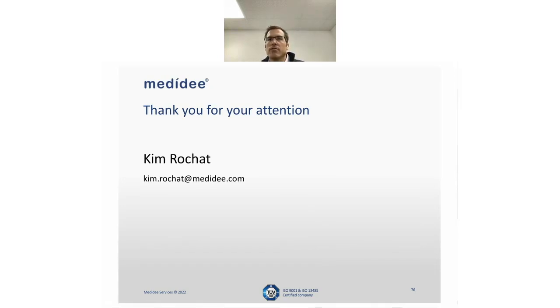I take the question of Stephanie. What is the situation if you add a medical software to an existing medical or combination product? If the intended use stays the same, but the device can now track through the added new software, is the regulatory path the same, including the clinical evaluation? Yes. So if this new software that you will add to the existing software, you need to define its regulatory status. So maybe it's becoming a component of the system. Maybe it's becoming an accessory of the system. Maybe it's a single standalone device. So you will have to look.